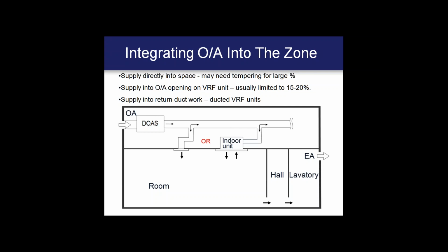All manufacturers have a multitude of different ducted type units, and again, fresh air can be introduced into the return ductwork, similar to how fresh air would be introduced into water source heat pumps or four-pipe fan coils. More commonly than not, though, a dedicated outside air system is being applied to at least temper or partially temper air before it's delivered to these indoor units or to the space, or at a minimum an energy recovery type ventilator, whether that's a larger centralized unit with a wheel, or a decentralized unit with a fixed core.